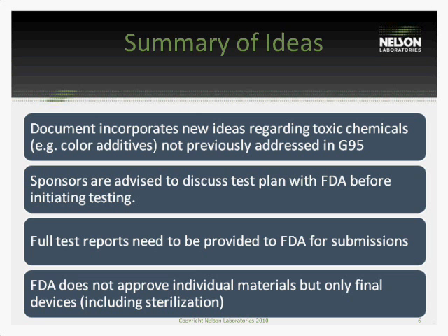But the FDA has always had, or recently has had, a specific concern about colors. Color additives are known to be potentially carcinogenic or genotoxic, and so we've had questions come back on devices that have colors in them, with the FDA wanting to see how much color leaches off the device, how much of that colorant interacts with the body, and what the safety impact is from a toxicological assessment.